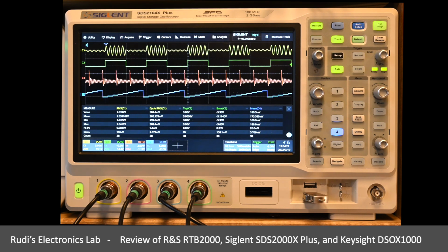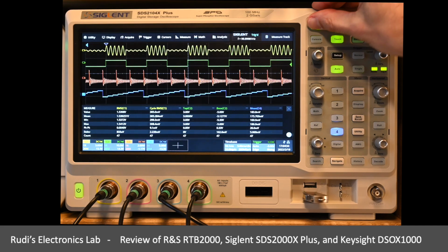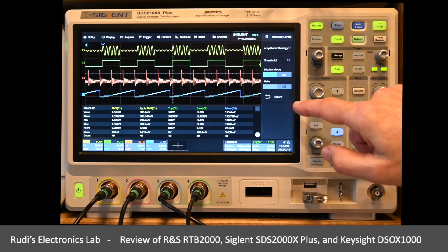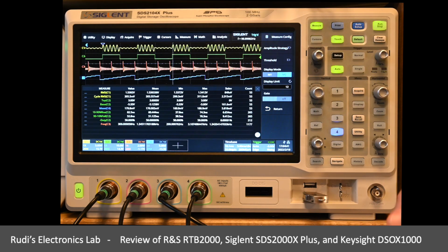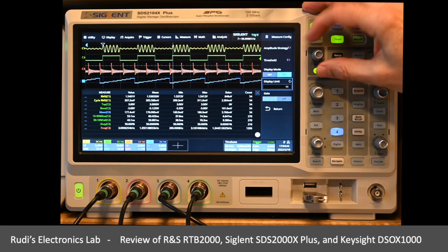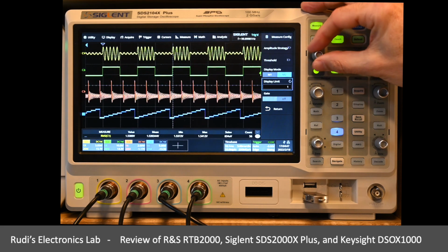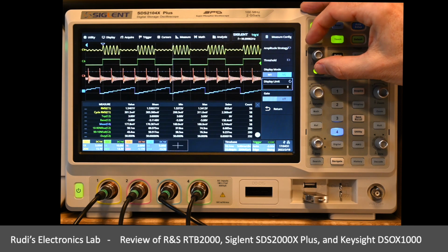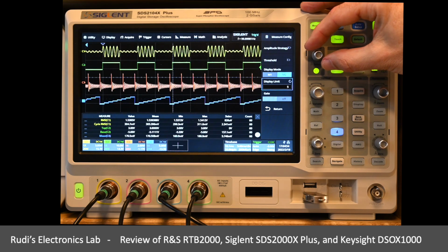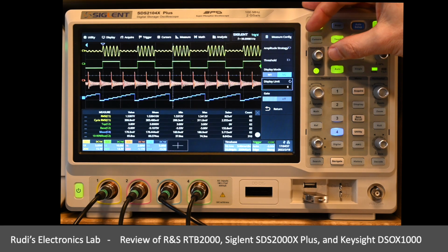I think we covered most of the measurement functions. There are a couple more things, and you'll find it in the background document, particularly also the M12 mode with more measurement positions and how that is laid out on the screen. Yeah, we can actually still take a quick look there. So we go to the... Actually, you could call it M5 or M12. I think that would have been a little bit more obvious. So here we can simply choose the number of positions that we would like to get and see. And we could actually put it at 5 or so. And so we get the maximum screen size that we would like to have here.